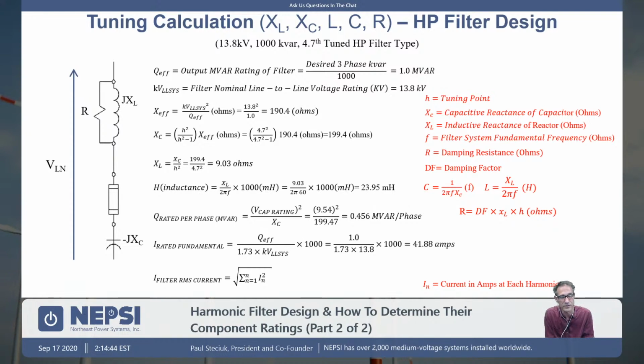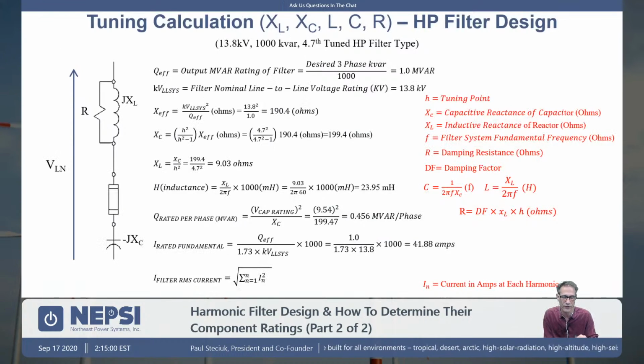But when the system has, say, interharmonics, or there are concerns for resonance associated with stray capacitance, then we oftentimes go with high-pass harmonic filters, and we add this value of resistance here. That value of resistance is determined first during the study simulation process. We're determining, well, what value of R do we need? Usually the process starts where you start with a high value of R, which if you think about a high-pass filter, if it's an infinite R, then it's a notch filter. We start to decrease the value of R, and we look to get adequate performance. As you decrease R, the losses in that resistor go up, and that's really the issue here. We're trying to minimize the losses, the 60 hertz or 50 hertz losses, that fundamental losses within the system.